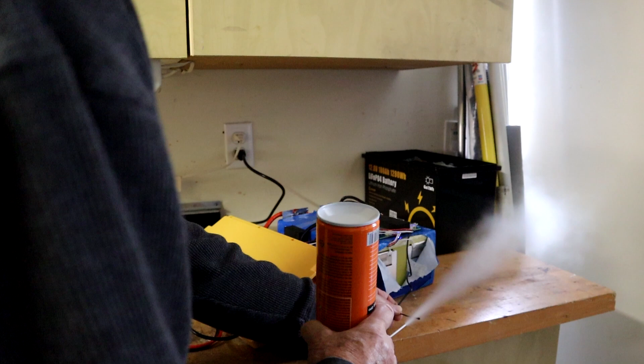Let me repeat that just to see if we get the same result. Minus 30, and it shut off. Where does it come back on? Somewhere around minus 7 degrees C it turned back on, which is right around 19.4 degrees Fahrenheit. So it doesn't seem to want to shut off until it gets definitely below 20 degrees Fahrenheit, which is probably not a good idea.